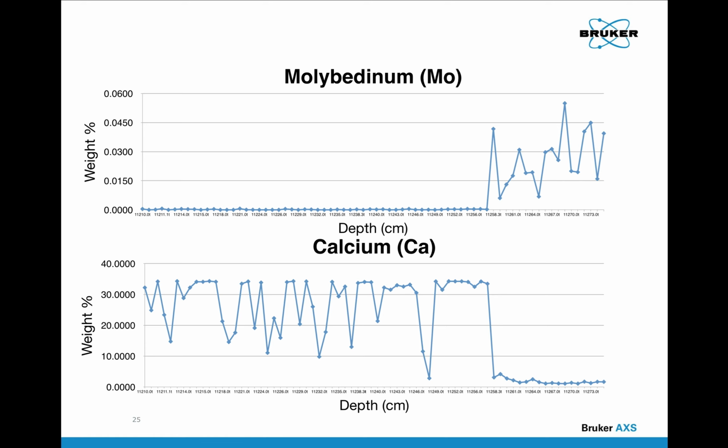And remember, rule number 1, your spectrum must be taken with the same parameters: energy, current, filter, and atmosphere. Second, your reference set must be within the minimum and maximum of every element that you expect in your sample.